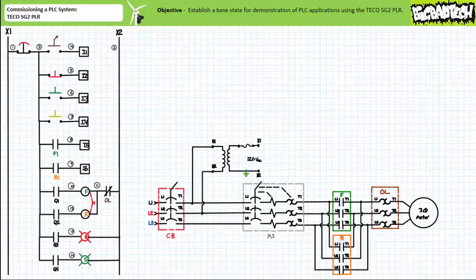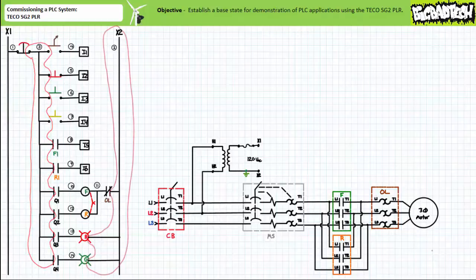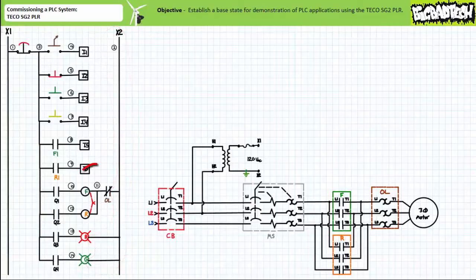Note the schematic kind of leaves unsaid what actually opens or closes the Q1 through 4 contacts. This is again meant to imply that isolation exists between the PLC and the output, and the program is in charge of actually opening and closing these contacts. All a technician needs to do is wire the devices as indicated. Wire numbers can again be used to further clarify points of connection. Note wire 3's pooled connection has expanded to include all the upstream terminals of the electromechanical relay outputs Q1 through Q4, and that wire 2 is the pooled connection of all field output device return paths. Additionally, note that the F and R contactor coils are mechanically interlocked together, preventing their simultaneous closure, and both contactor coils are serviced by the same normally closed overload contact.